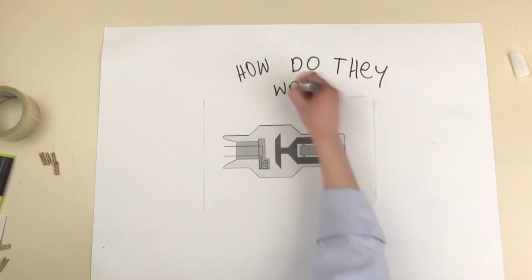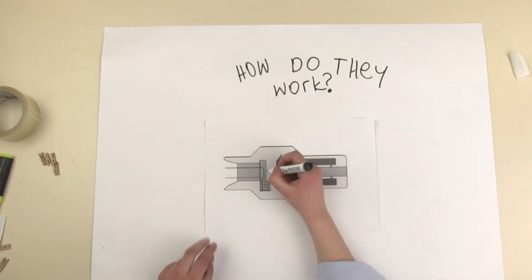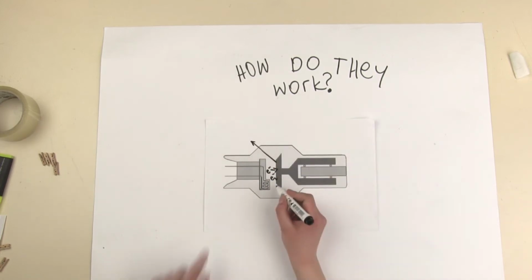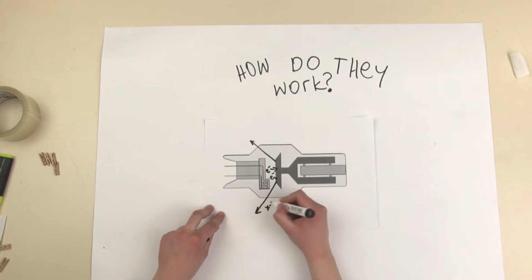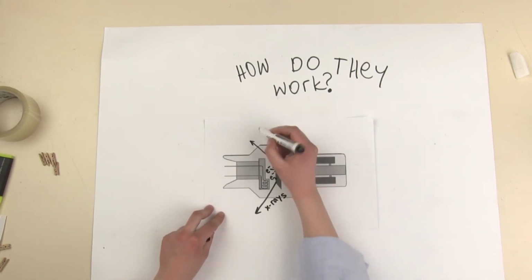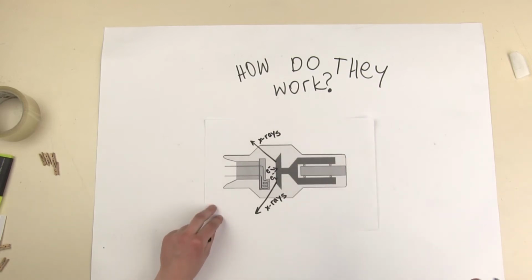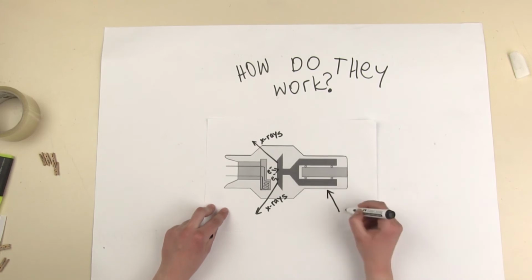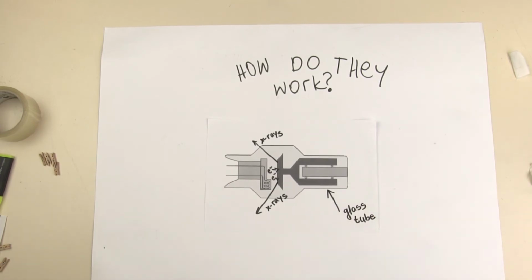How do they work? The rays come from an artificial source, the X-ray tube, a type of electronic lamp analogous to a diode lamp device. It is a glass tube in which a vacuum is created. The cathode is a metallic element heated by a thin spiral wire, or the spiral wire itself is the cathode, from a separate low voltage heating circuit up to several hundred degrees Celsius, visually to red.